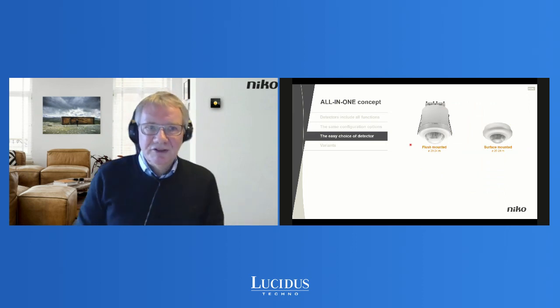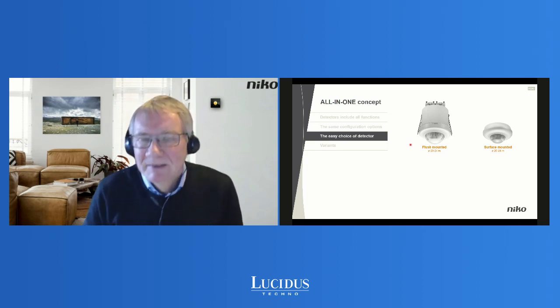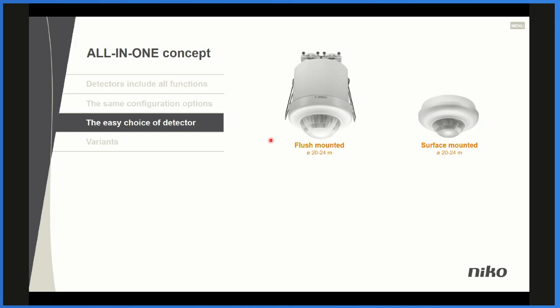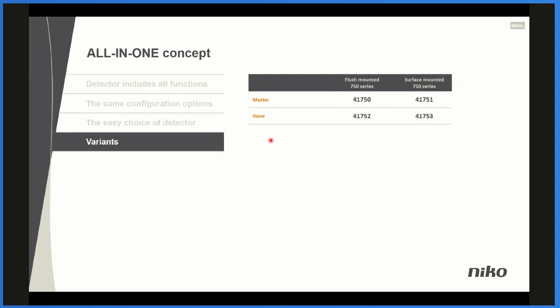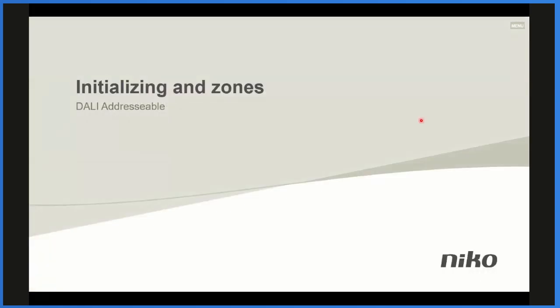If you want the ease of choice of detectors, there are two different options, either for flush mounting or for surface mounting. I would say that both of them are IP54, so they can be used in every environment for indoor use. We offer one master for flush mounting and another for surface mounting, and then you have the slaves, which are okay for both flush mounting and surface mounting. These detectors are according to the IEC standard 62386, and that means they follow exactly the same rules for how they have to be installed and initiated and so on.